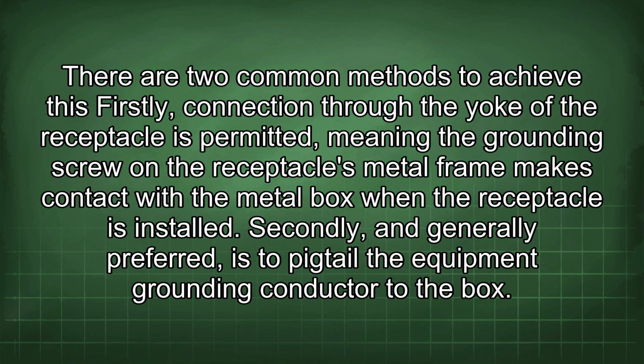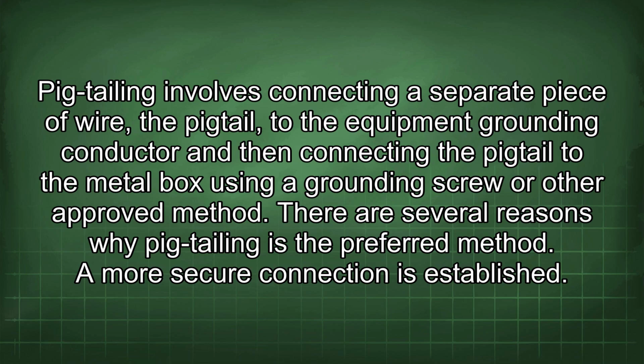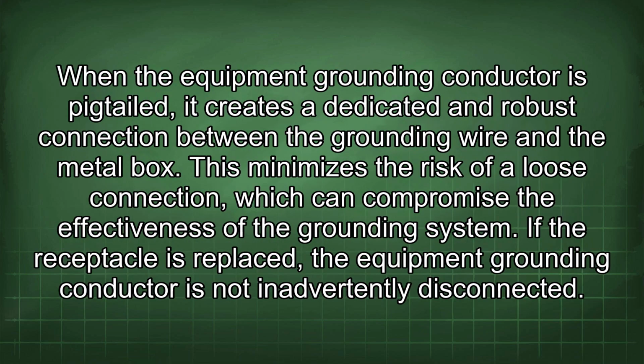Secondly, and generally preferred, is to pigtail the equipment grounding conductor to the box. Pigtailing involves connecting a separate piece of wire, the pigtail, to the equipment grounding conductor and then connecting the pigtail to the metal box using a grounding screw or other approved method. There are several reasons why pigtailing is the preferred method. A more secure connection is established. When the equipment grounding conductor is pigtailed, it creates a dedicated and robust connection between the grounding wire and the metal box. This minimizes the risk of a loose connection, which can compromise the effectiveness of the grounding system.